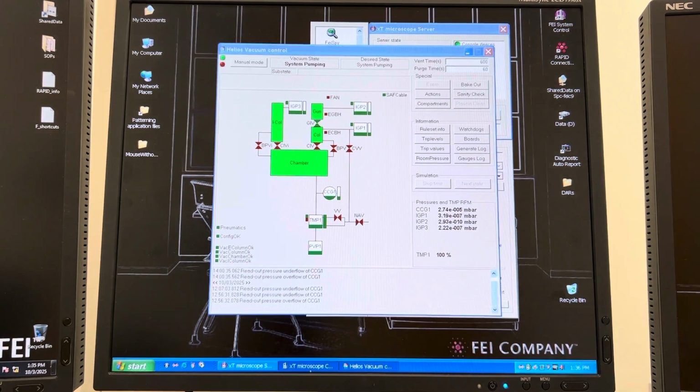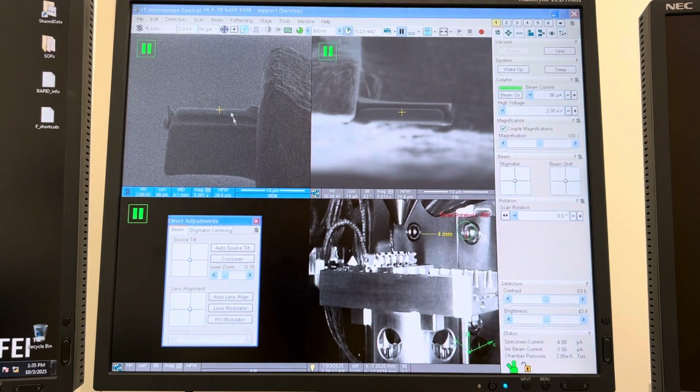that will randomly turn off. Sometimes that's a sign that the pre-vacuum pump is failing and needs to be replaced. It depends on how frequently it happens, but I've seen this happen specifically on this system occasionally, and apparently it happened within the last day or so. So anyways, you're kind of between a rock and a hard place at this point, and really you just gotta wait.